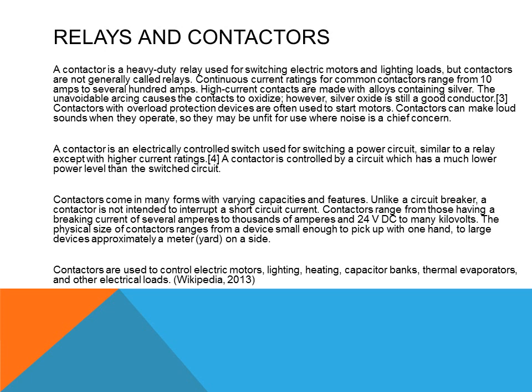The difference between a relay and a contactor: contactor contacts are normally open and will close when the coil energizes. Relays can have many different contact configurations, such as single pole single throw, single pole double throw, or double pole double throw — any combination to do work or to transfer and divert current to different areas.